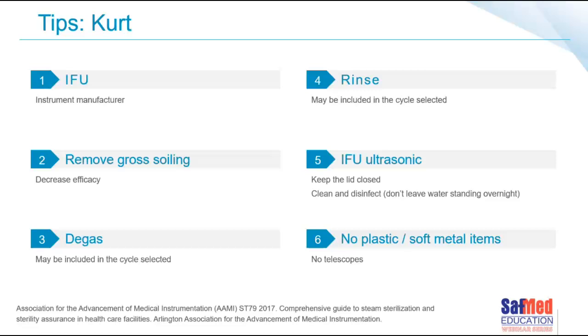So number 5, a lot of the ultrasonic cleaners or certain brands will have a sensor on the ultrasonic cleaner, so it asks you to keep the lid closed. Keeping the lid closed during operation, of course, eliminates any aerosols being pushed out from the ultrasonic cleaner into the CSSD area and us inhaling those aerosols from the cleaning. So always keep the lid of the ultrasonic cleaner closed. A lot of them have sensors, so if you open the lid, it will stop the cleaning process immediately and abort the cycle. But if it's a manual one, some of them are older, please do not leave the lid open. It creates a lot of aerosols.